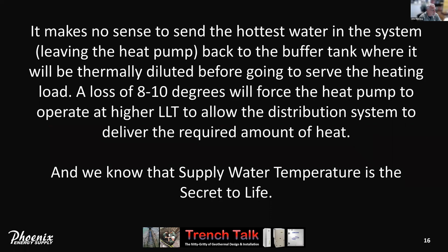It makes no sense to send the hottest water in the system, that leaving the heat pump, back to the buffer tank where it will be thermally diluted before going to serve the heating load. A loss of 8 to 10 degrees will force the heat pump to operate at a higher leaving liquid temperature to allow the distribution system to deliver the required amount of heat. And we know that supply water temperature is the secret to life.